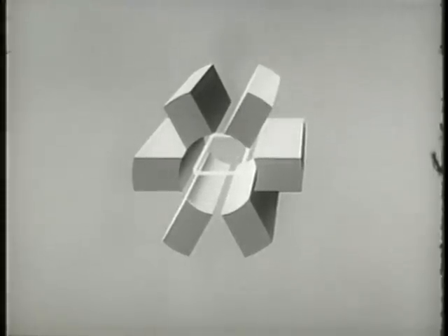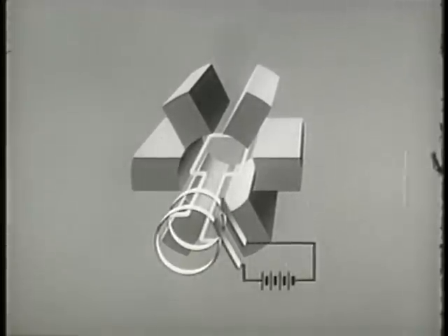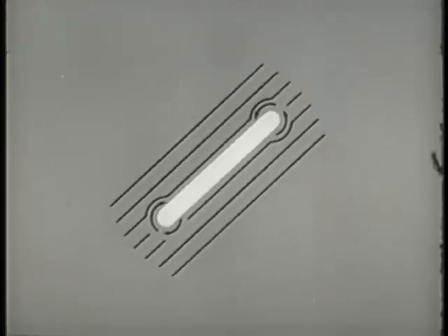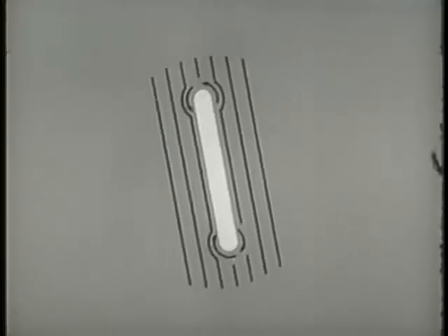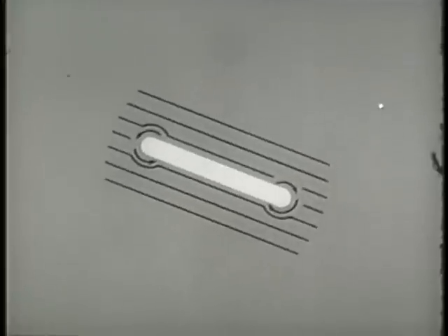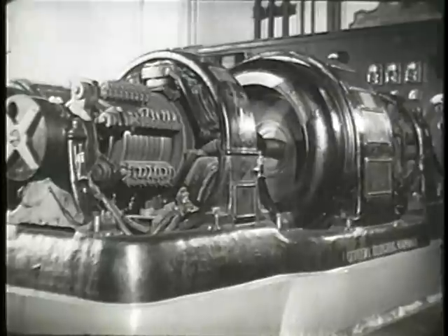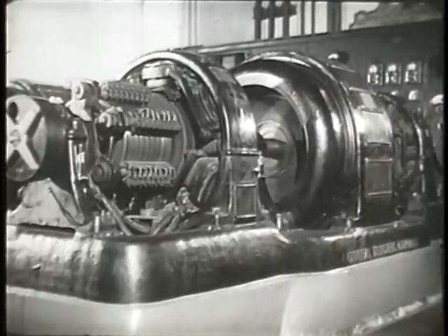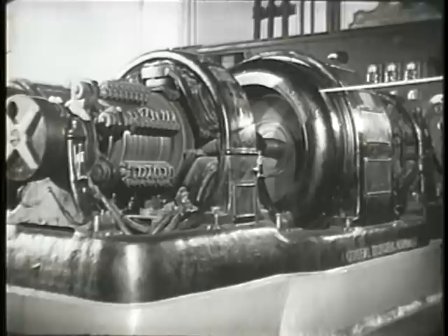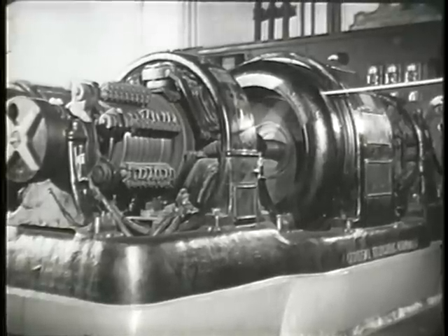In the synchronous motor, however, a different situation exists. Here, a multiphase source of AC is applied to the stator windings, producing a rotating field, and a separate DC voltage is applied to the rotor windings, producing an independent magnetic field. There is no need for relative motion here. The synchronous motor is so designed that the rotor and the field rotate at the same speed. This is of importance when synchronous motors are used to drive equipment requiring this characteristic.